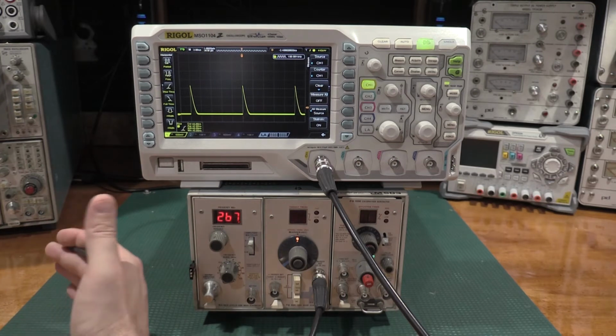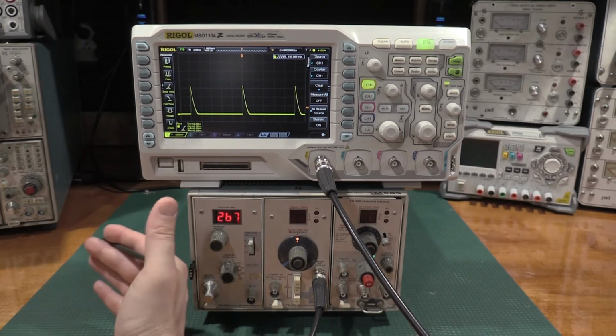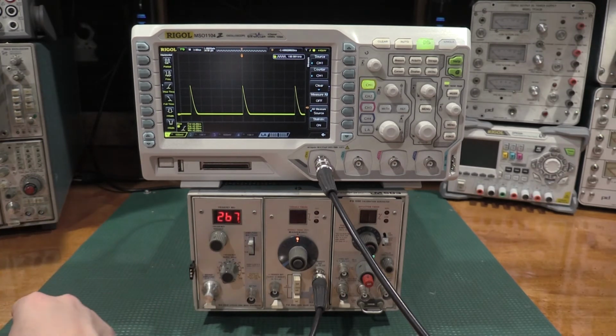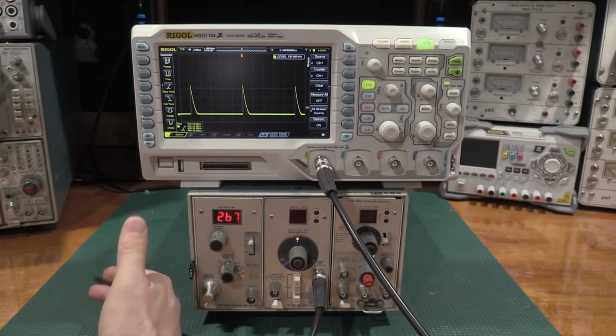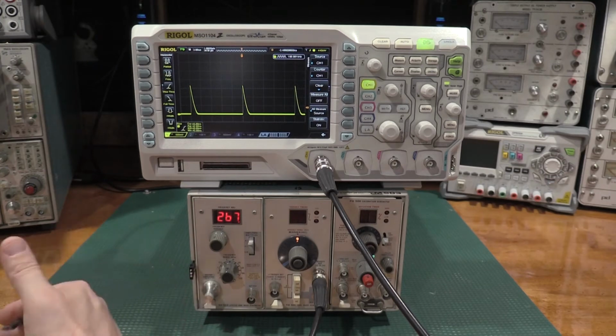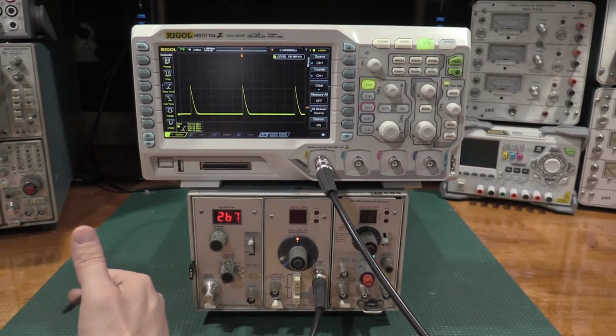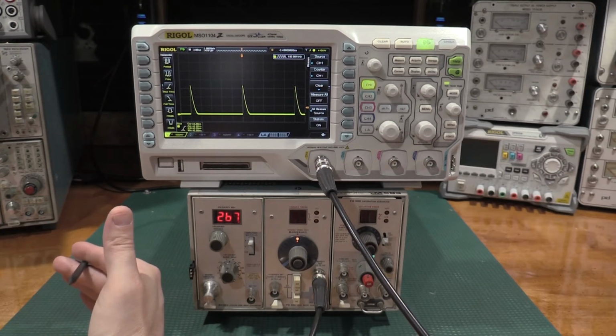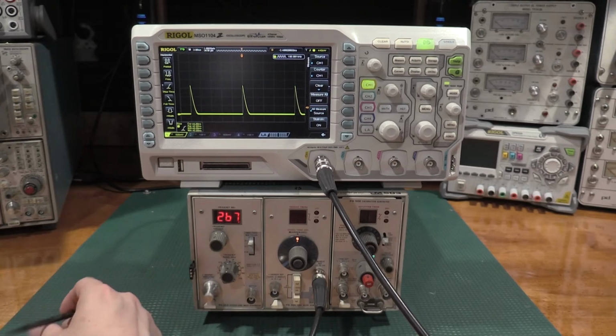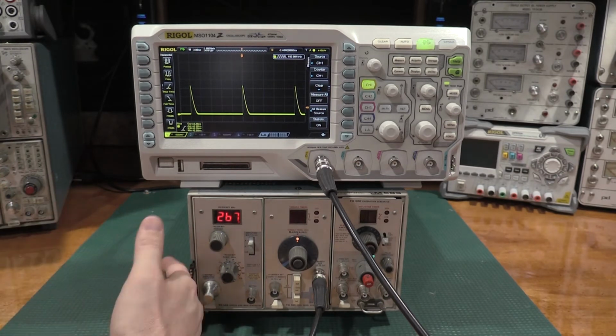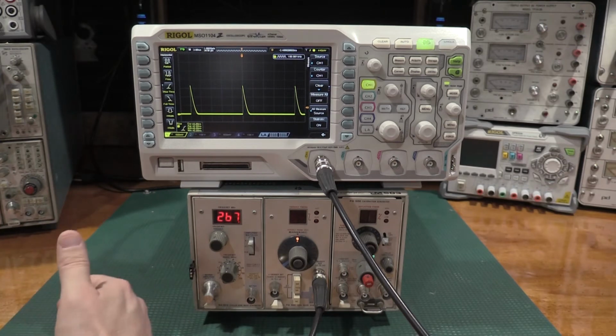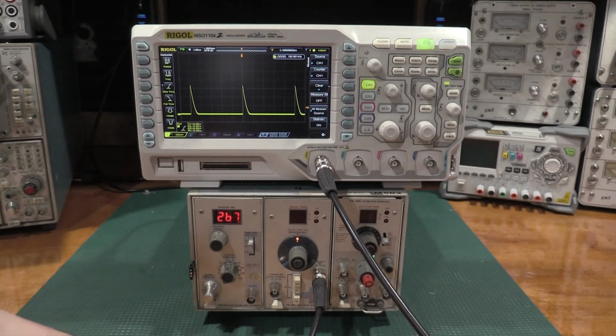And then with those, typically what's done is a program's written. You go through the cal document of the scope, the program literally just steps through the process, and then you adjust the correct control for whatever the waveform is. Hit next, it goes to the next step. Adjust the control, whatever the waveform is, next, and you just step through the process. At the end of the day, the scope's done.